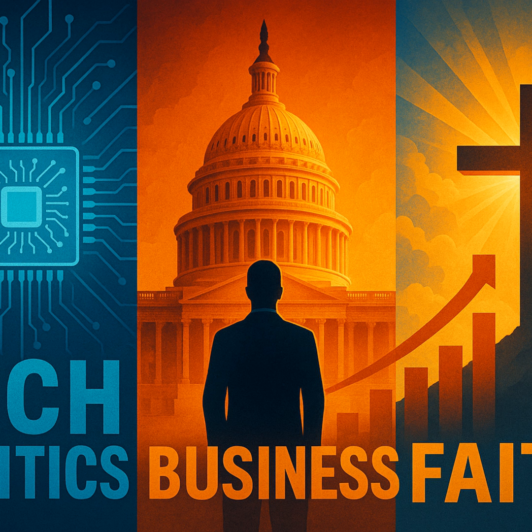Can you give us a concrete example where this GFM tech really made a difference? Yeah, the incident in Hawaii in 2023 is a perfect case study. On the island of Oahu, a huge conventional power plant, something like 208 megawatts, suddenly tripped offline, just dropped out. Okay, that's a massive loss of power for an island grid.